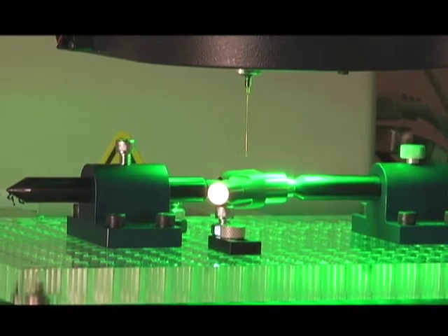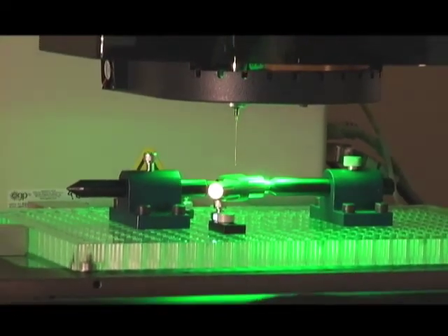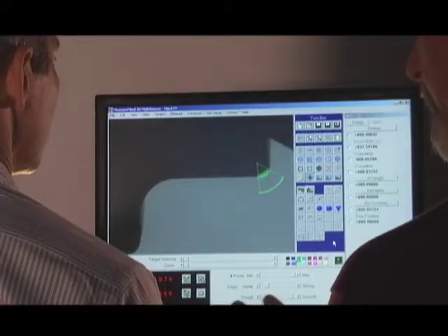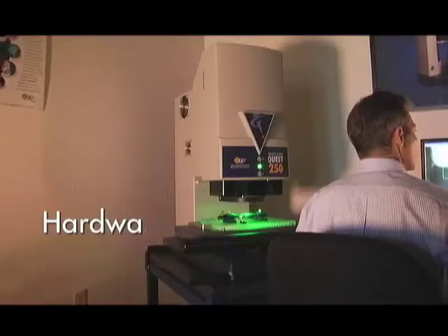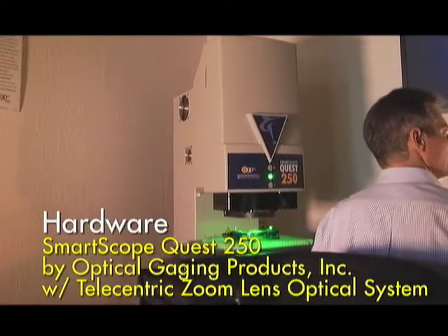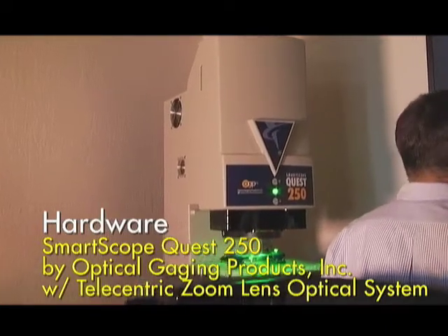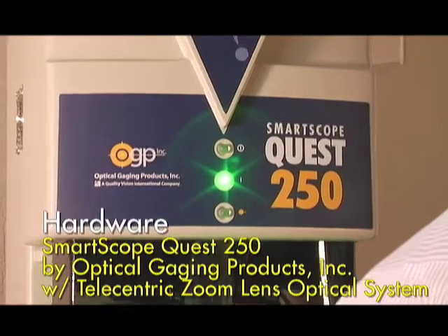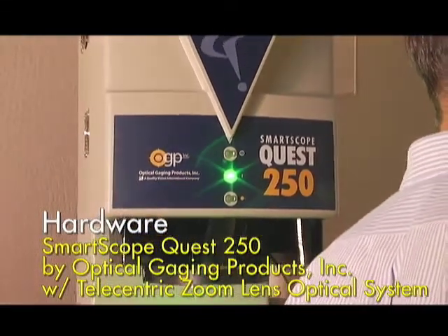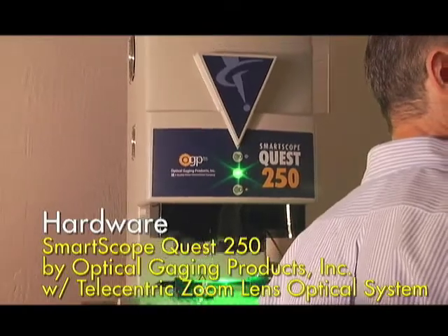One of the unique things about the Quest is its optical system. The SmartScope Quest does represent the high end of the Optical Gaging Products offerings for general purpose vision and multi-sensor systems. It's a fully telecentric relay zoom lens. What does that mean? Well, for us dimensional measurement guys, what it really translates into is that it's harder to make a bad measurement. So this is multi-sensor again, is that correct? This is also a multi-sensor system. The SmartScope product line is all general purpose multi-sensor systems. The sensors we're using here today will be the vision system as well, going through the telecentric relay zoom lens.